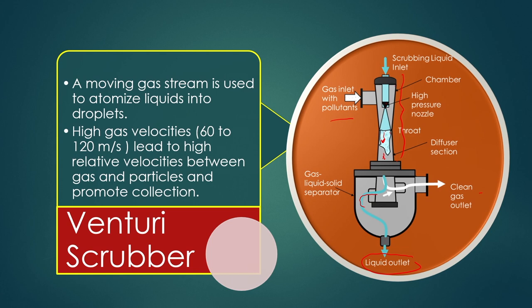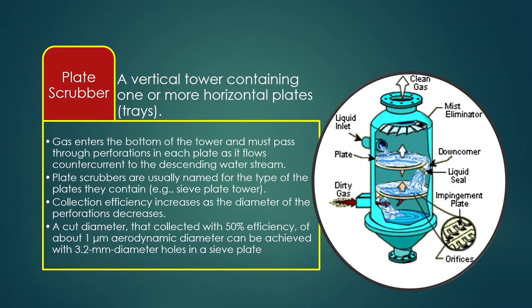The main mechanism of the venturi scrubber is that the moving gas stream is used to atomize liquids into droplets, and high gas velocities around 60 to 120 meters per second lead to high relative velocities between gas and particles, promoting collection.